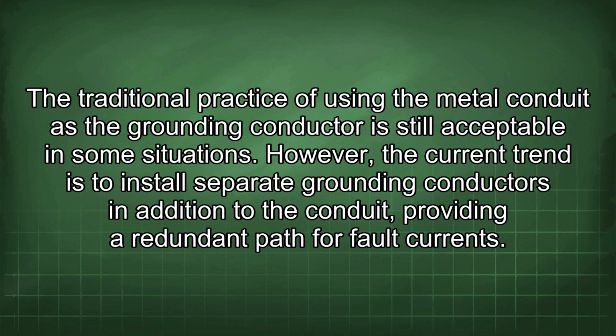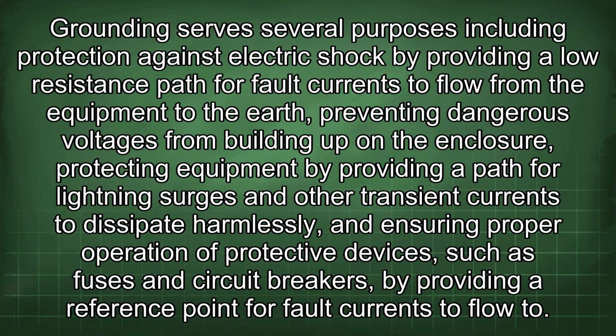fault currents. Grounding serves several purposes, including protection against electric shock by providing a low-resistance path for fault currents to flow from the equipment to the earth, preventing dangerous voltages from building up on the enclosure, protecting equipment by providing a path for lightning surges and other transient currents to dissipate harmlessly, and ensuring proper operation of protective devices, such as fuses and circuit breakers, by providing a reference point for fault currents to flow to.